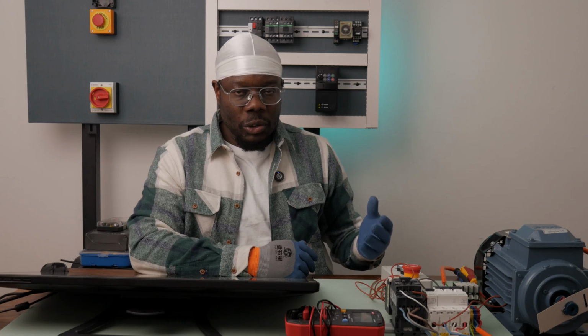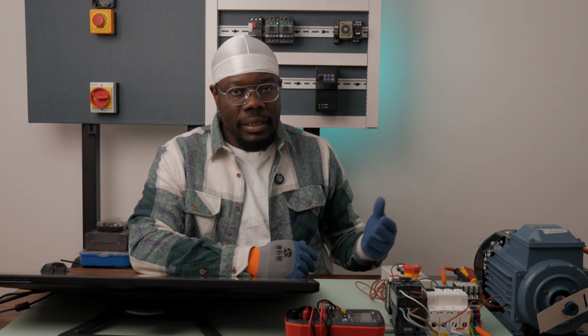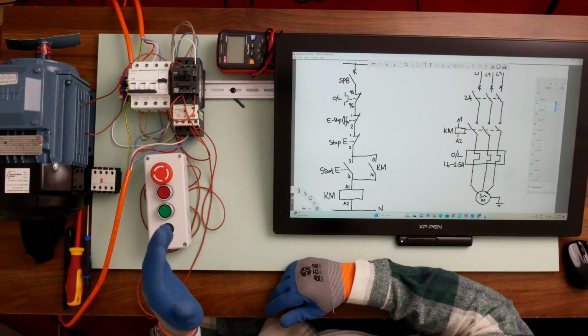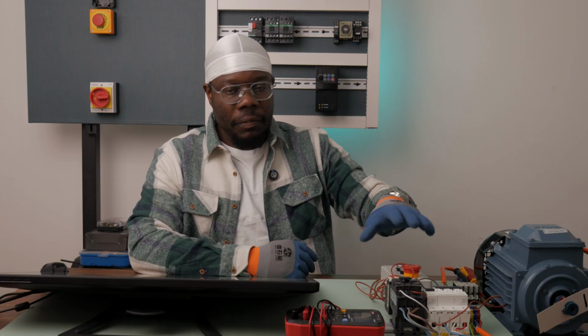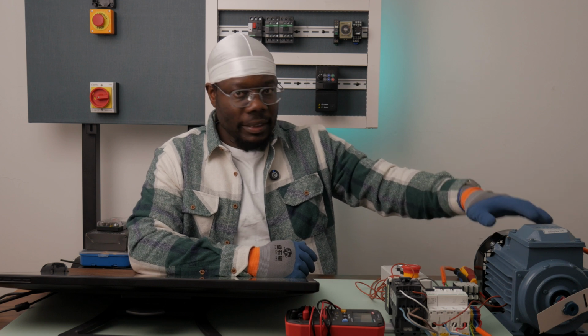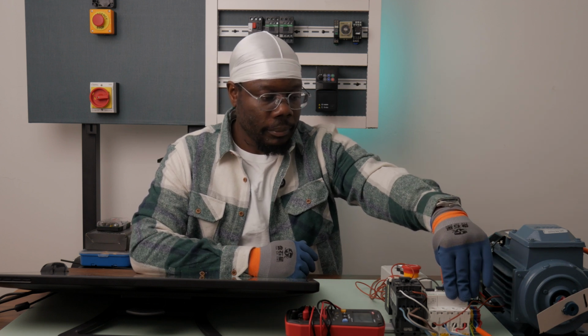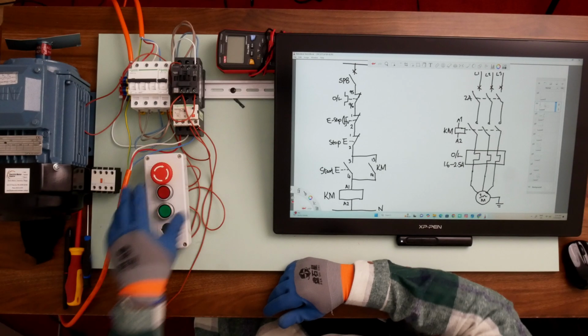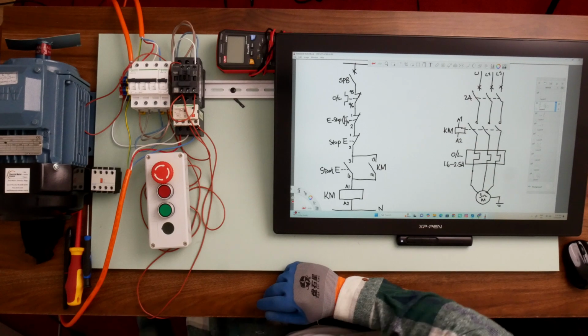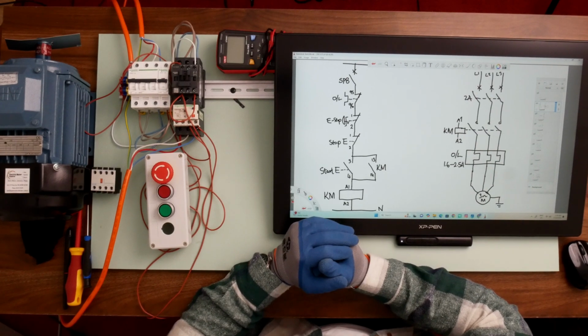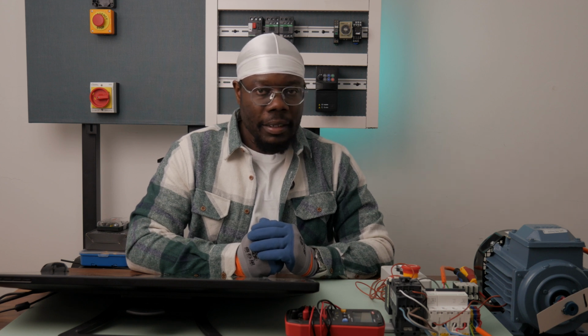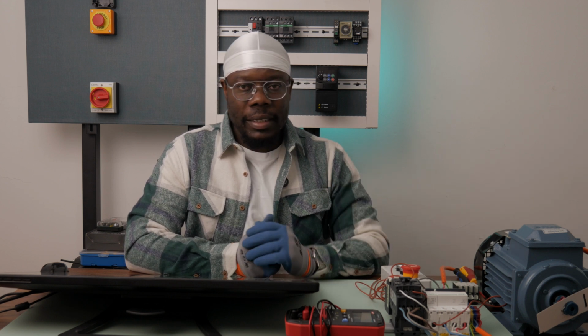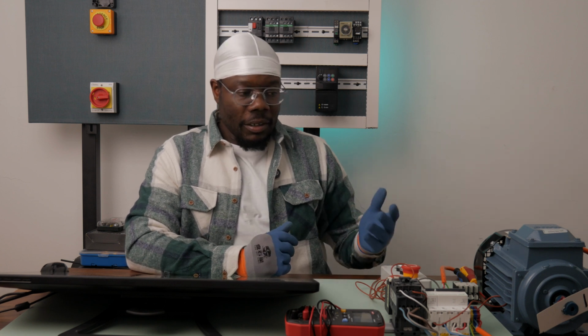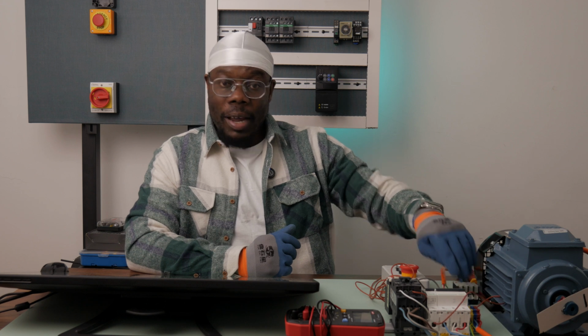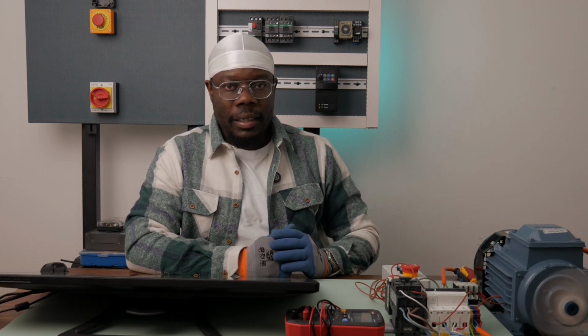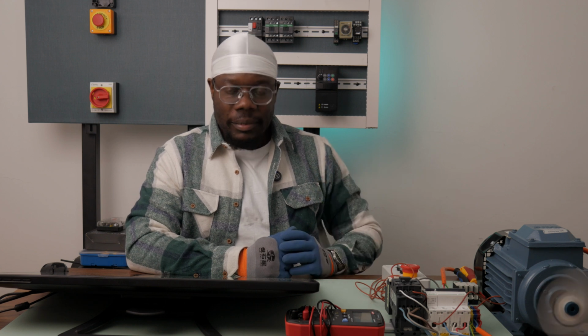So that's an assurance that my electric motor is not going to restart on its own. All right, now I'm going to switch on my 3-phase power so that we can run this electric motor and see if we've done the correct thing. If you can hear a little fan running, that's from my variable speed drive, which is providing us with the 3-phase power. So let's start our electric motor and see if we've done the right thing. See, it's running. So bingo, it's going well.